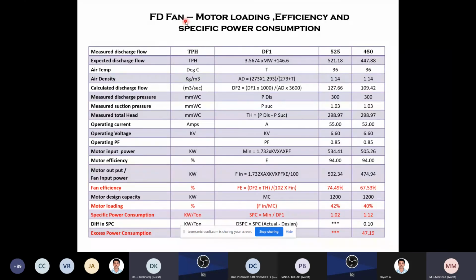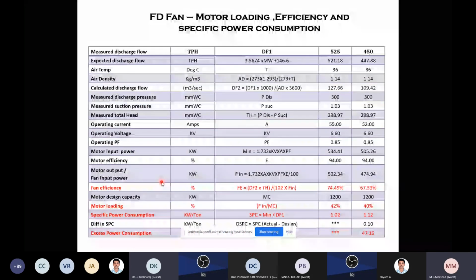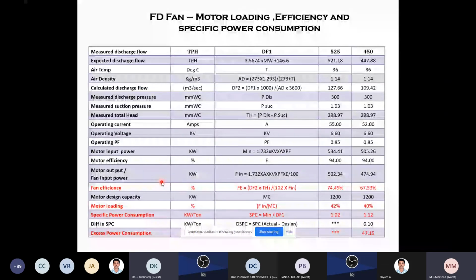FD fan data you have to collect everywhere. What is the air density, the discharge flow, air temperature, density, discharge pressure measurement, suction pressure. These are the data you have to collect from the local instruments itself, or if it is available in the DCS, you can collect it from there. Then you have to calculate the fan efficiency.